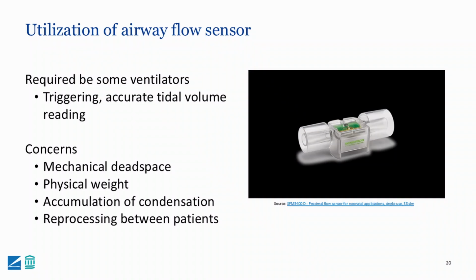There is physical weight of these flow sensors, which can lead to kinking or displacement of endotracheal tubes in neonates, especially when they're very, very small and pliable. Once they get in a heated isolette, they become very pliable, and so that physical weight can actually be very problematic. Humidification is important, and all ventilator circuits, especially in extremely low birth weight neonates, should be heated wire circuits. But the airway flow sensor is not heated, and so you have some degree of cooling, which then produces condensation as gas flow travels across the airway flow sensor. This again is right on the airway, and so any of that cooling and condensation of water vapor then can actually lead to aspiration into the patient's endotracheal tube, again causing significant tidal volume loss, desaturation, and bradycardia.